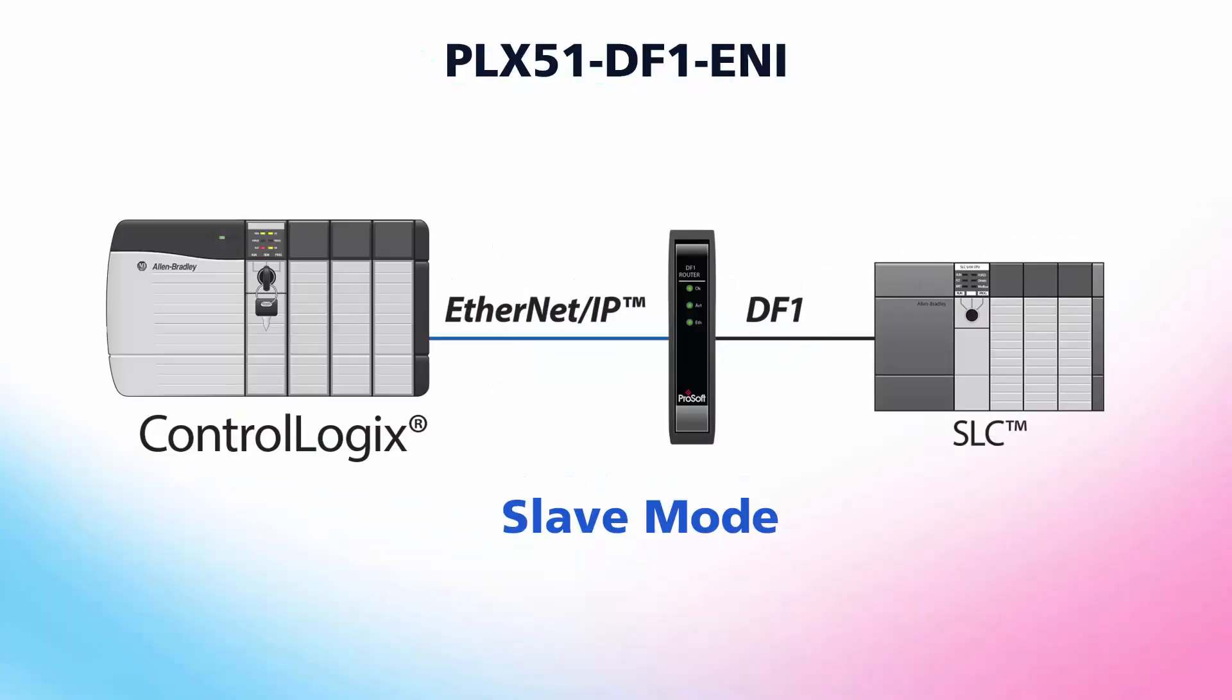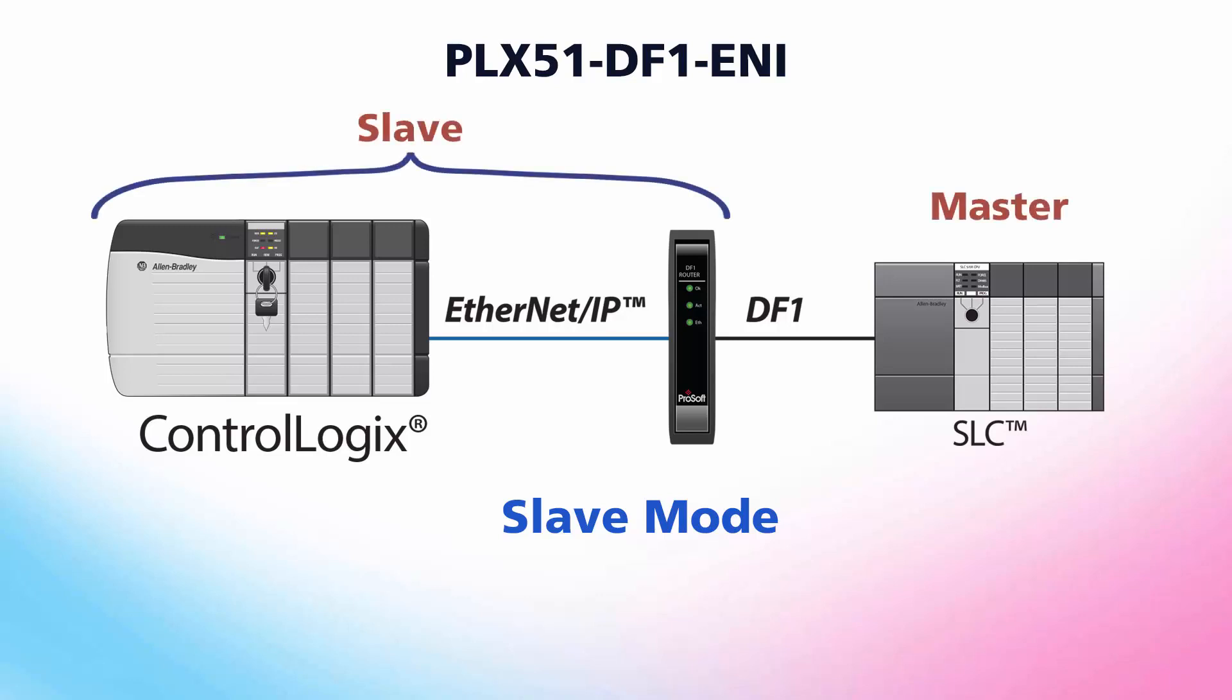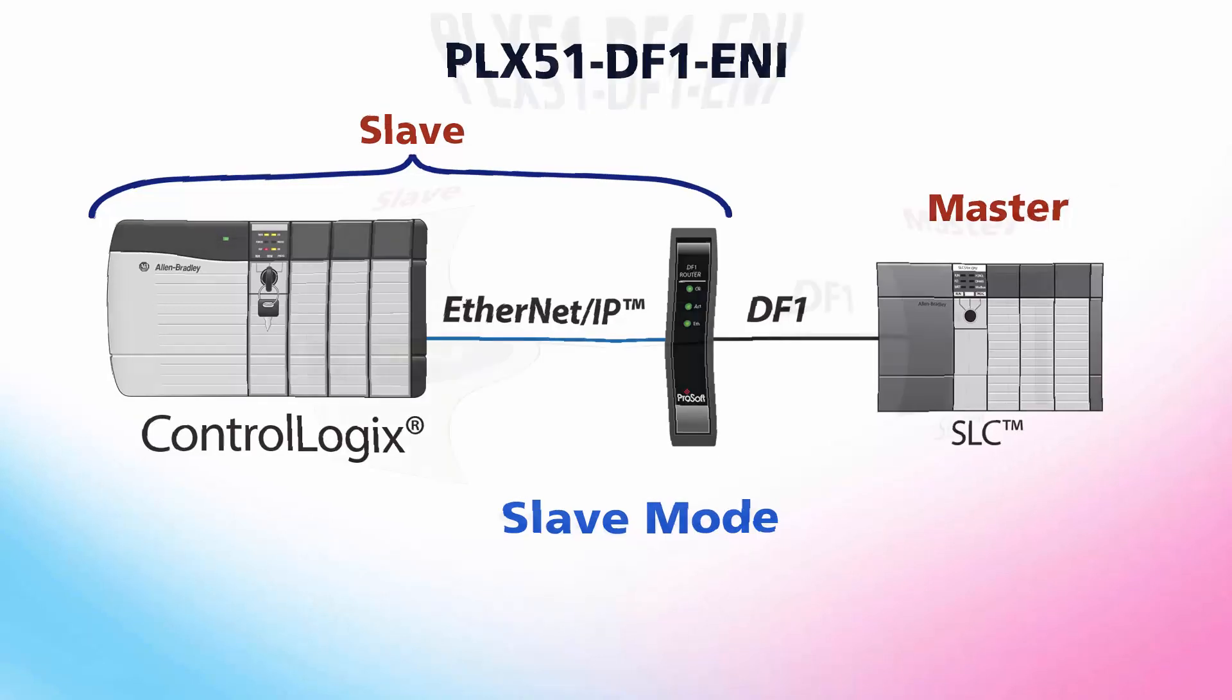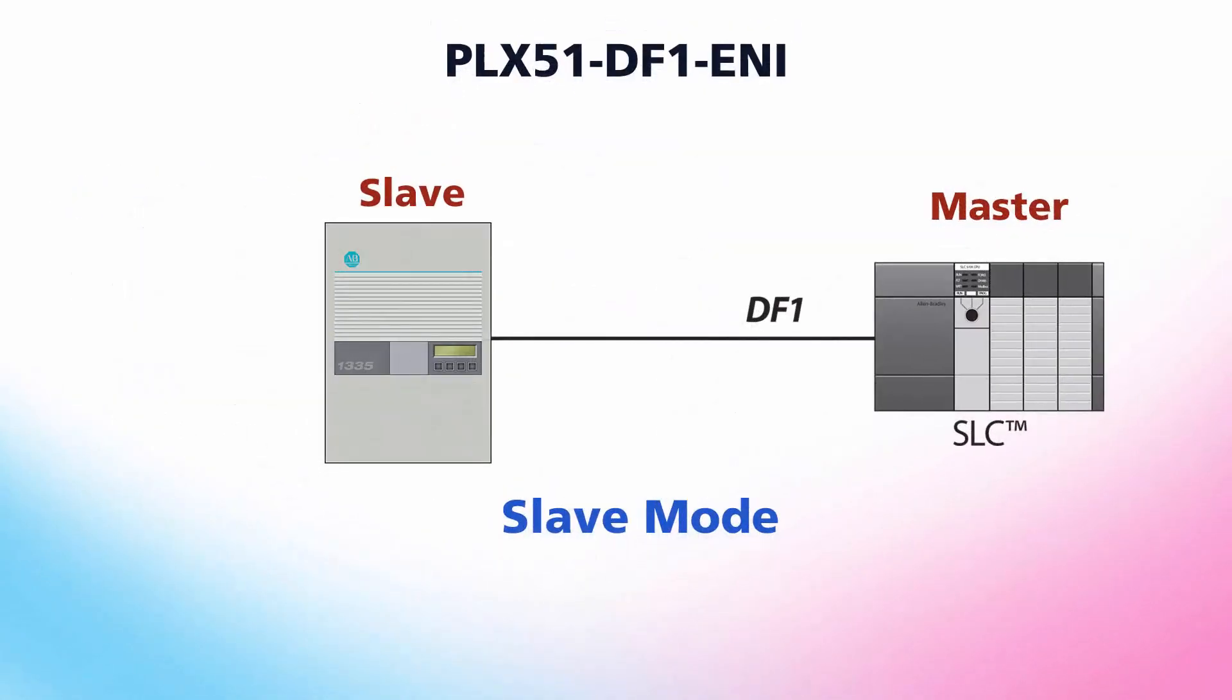Today we'll go over the general setup for the PLX51, and then cover how to set up the gateway in DF1 slave mode. In this configuration, our gateway will act as a slave on the DF1 network, allowing a DF1 master to read and/or write data to one or more Logix controllers. Essentially, the Logix controller will be seen as a DF1 slave by the DF1 master. It's very handy if you're upgrading from MicroLogix controllers or SLC 500s.